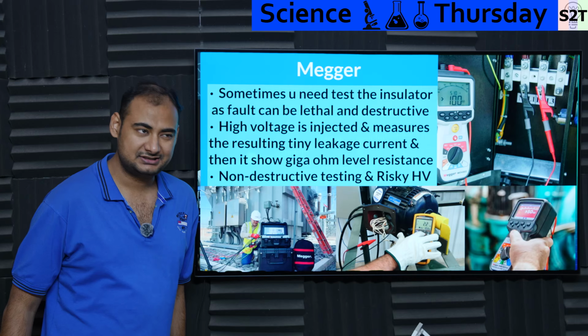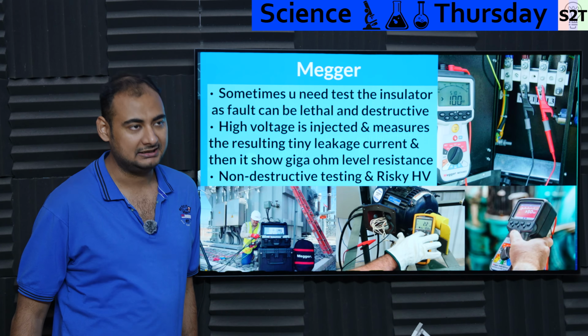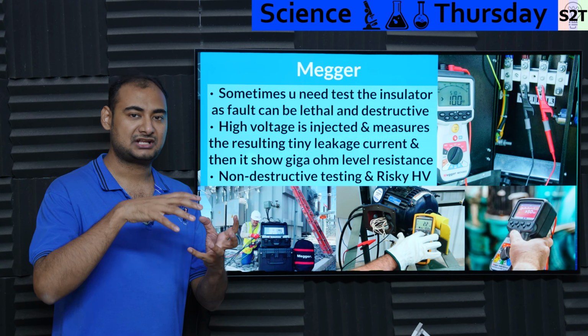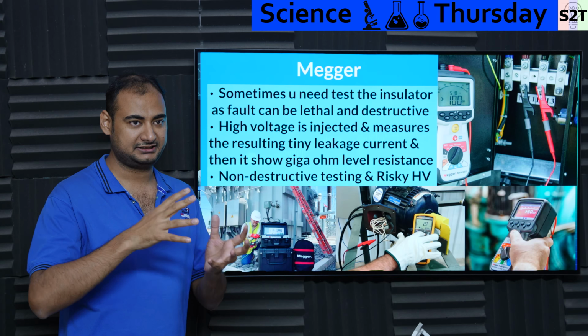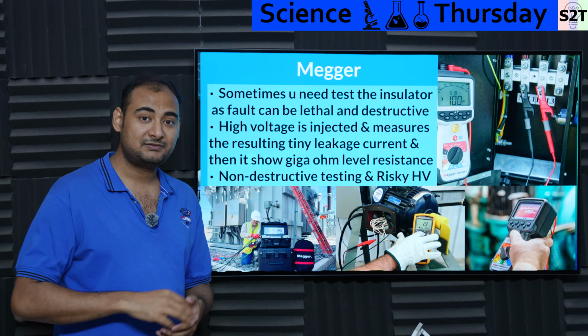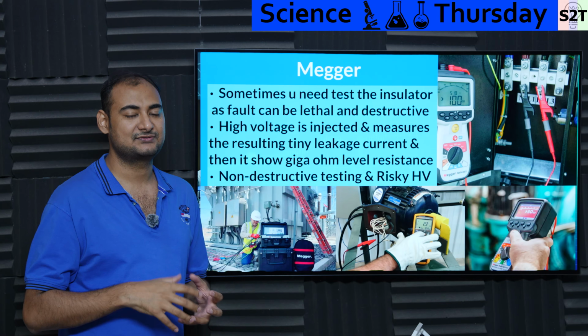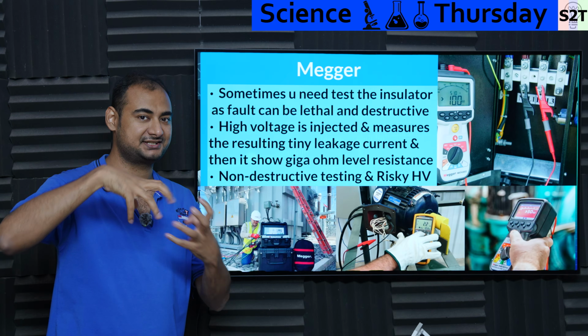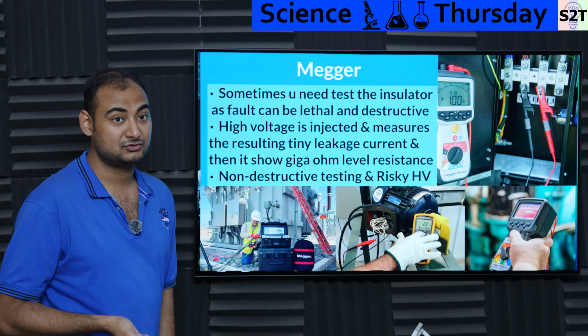And this is one of the few things that can tell you the health of the insulation. Meaning a transformer expands and contracts day and night, so that has some wear and tear. On top of that, because of loading and unloading of the transformer, it also flexes -- the coil itself flexes. So over time, the insulation becomes weaker.